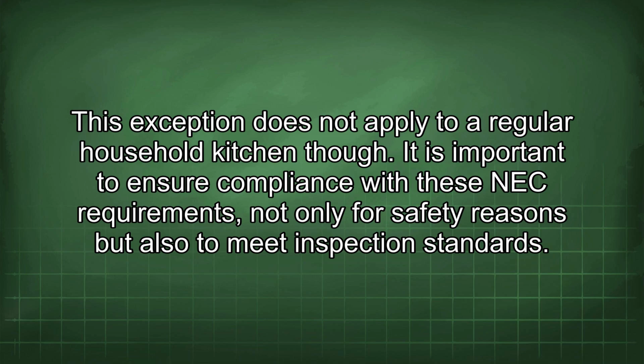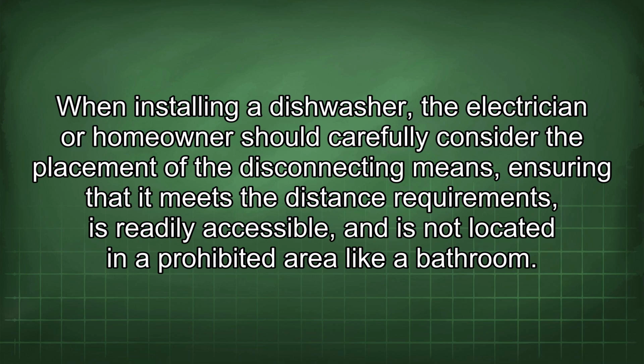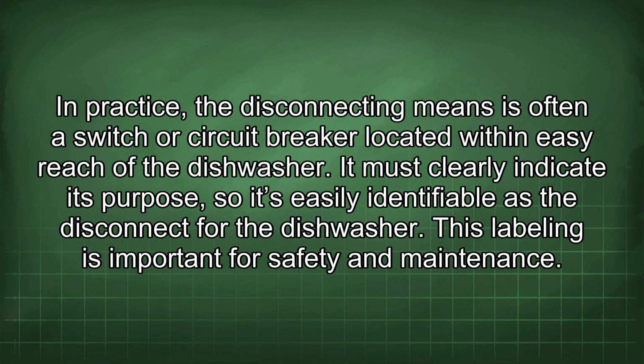It is important to ensure compliance with these NEC requirements, not only for safety reasons but also to meet inspection standards. When installing a dishwasher, the electrician or homeowner should carefully consider the placement of the disconnecting means, ensuring that it meets the distance requirements, is readily accessible, and is not located in a prohibited area like a bathroom. In practice, the disconnecting means is often a switch or circuit breaker located within easy reach of the dishwasher. It must clearly indicate its purpose, so it's easily identifiable as the disconnect for the dishwasher. This labeling is important for safety and maintenance.